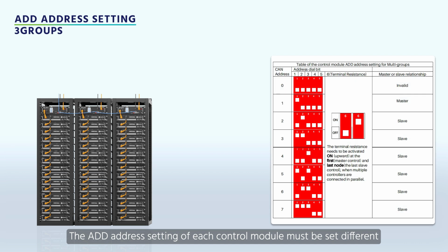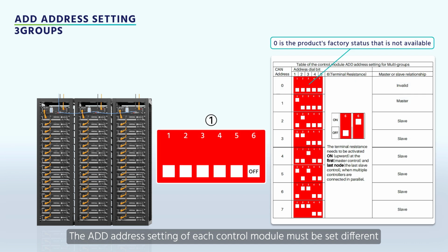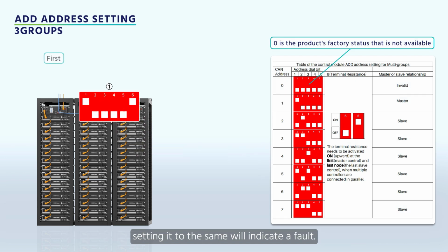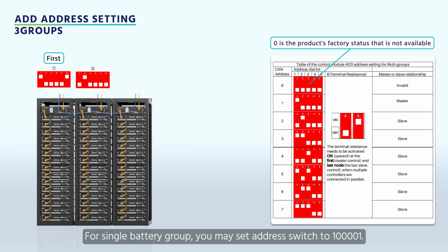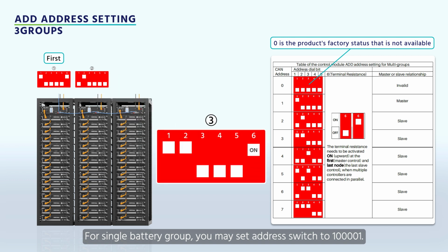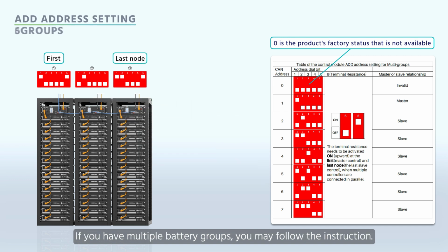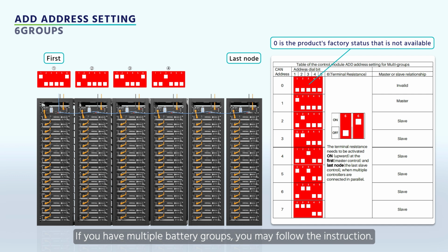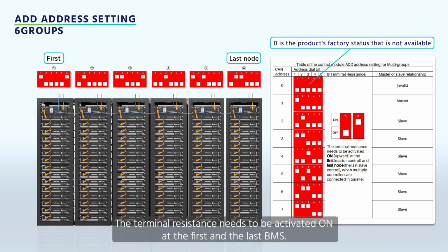The ADD address setting of each control module must be set differently. Setting it the same will indicate a fault. For a single battery group, you may set the address switch to 100001. If you have multiple battery groups, you may follow the instruction. The terminal resistance needs to be activated on the first and the last BMS.